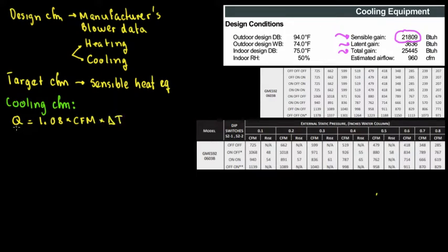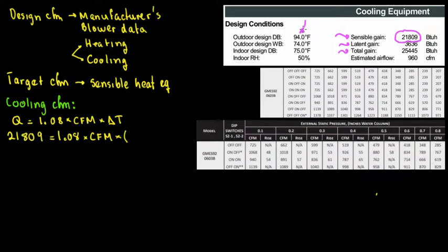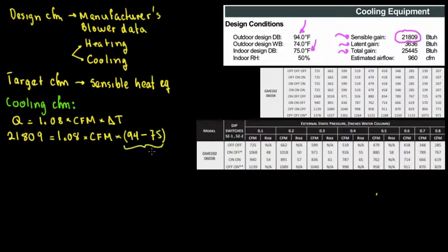My sensible heat is 21,809 BTUs per hour. That equals 1.08 times cooling CFM times delta T. The delta T is based on ASHRAE outdoor design temperature minus indoor design temperature — in this case, 94°F minus 75°F, which gives a temperature drop of 19 degrees Fahrenheit.